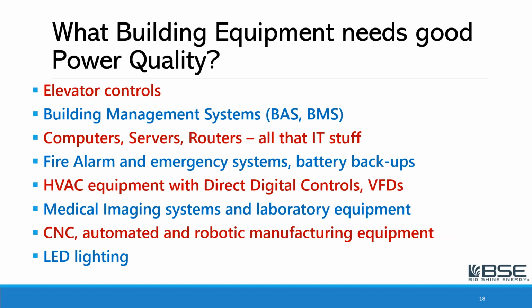So what kind of building equipment needs good power quality? And by the way, I should say that poor power quality is something you won't see with your eye. You won't know necessarily that it's going on, but I'm going to show you some waveforms that were captured with a special meter in a few minutes, and you'll get an idea of what bad power quality looks like. So every type of control: elevator controls, building management systems, all that IT stuff, computers, servers, routers, the fire alarm and emergency systems, battery backups, HVAC equipment with direct digital controls and VFDs, medical imaging systems and laboratory equipment, CNC or automated robotic manufacturing machines and equipment, and finally, LED lighting. All of those need good power quality, and all of those are sensitive and will have shortened life if the power quality is poor, or if the grounding system especially is poor.